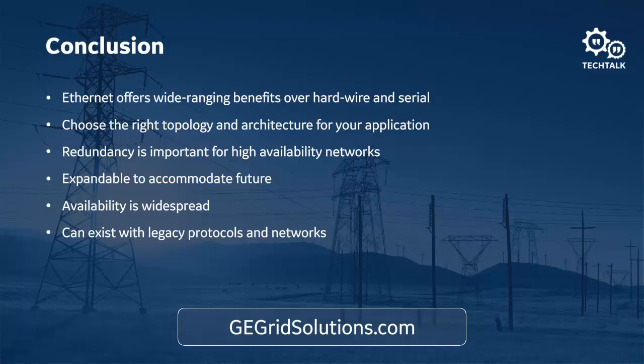Another question: what's the latency difference between Routable GOOSE and standard GOOSE? Standard GOOSE, being within the substation where you control all the latencies within your switch, is probably going to be faster. When you go outside the substation using Routable GOOSE, you're susceptible to the latencies of whatever technology you use in your wide area network. So routable GOOSE will generally have higher latency than standard GOOSE.